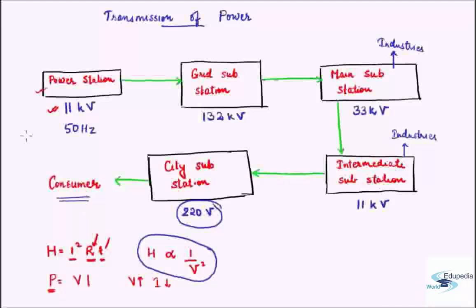Now as we have seen, from power generation to the whole transmission ending up in the consumer, the power is being carried through maybe thousands of kilometers, and therefore it is very, very important to take into account the heating losses, and as a result the need to step the voltage up to as high as 132 kilovolt. Fine. This gives you a rough idea about how the transmission of power works. Why do we step up the power voltage, and how do we step it down in steps at different substations.